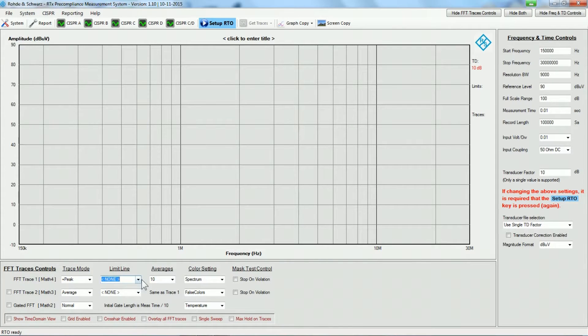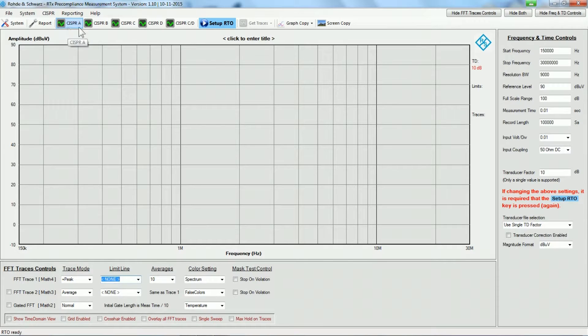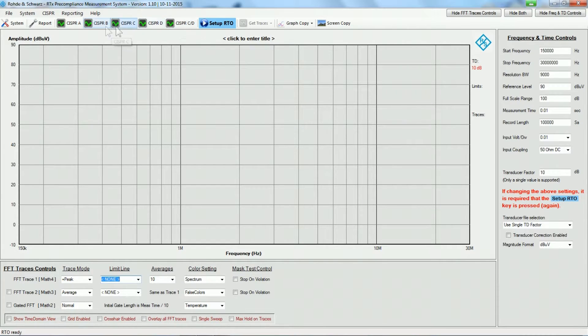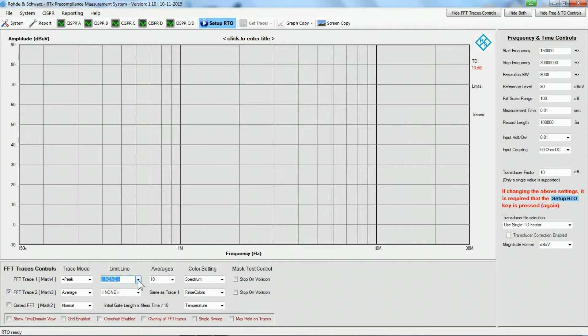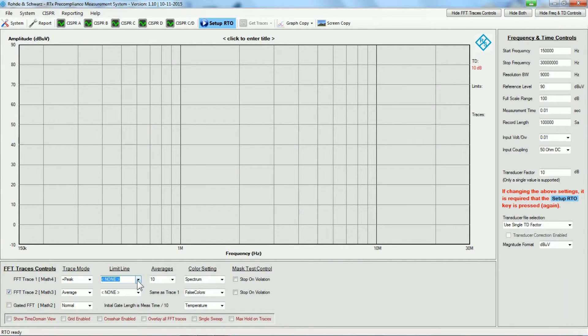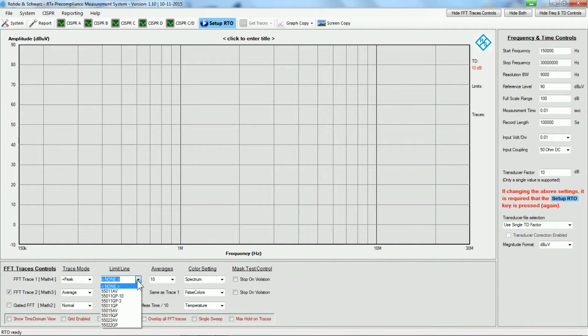In order to make it easy, I can select up here predefined CISPR bands, and I will click here on CISPR band B. That will set up the frequencies and the FFT traces. What we need to do is determine which standard I will be testing against. So let's say we are testing against EN55011.